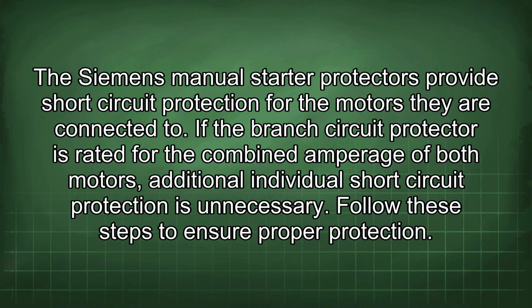Siemens manual starter protectors provide short circuit protection for the motors they are connected to. If the branch circuit protector is rated for the combined amperage of both motors, additional individual short circuit protection is unnecessary. Follow these steps to ensure proper protection.